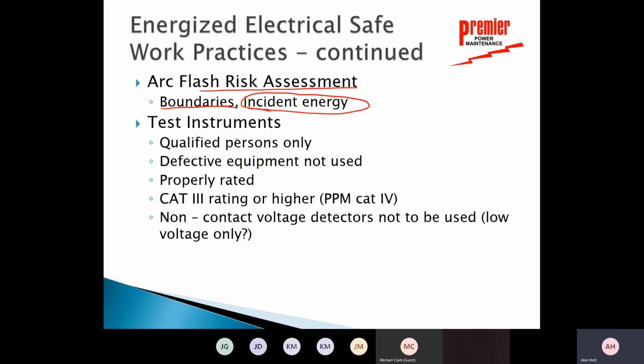When we're using test instruments, qualified persons only, they should be designated and utilized. We should know what we're doing. We don't use defective equipment. Everything's properly rated. Marathon has a requirement that all of our meters have to be Cat 3 rating or higher. We've done the meter safety in the last month, but all of Premier's meters should be Cat 4. Again, I mentioned non-contact voltage detectors are not to be used on low voltage. So you can't use a Wiggy or something like that to check for low voltage. And I don't believe that you can use it for the high voltage either, and Jay's confirmed that.